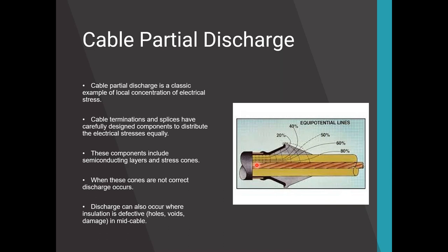The design of a cable and the stress cones and the terminations have a lot to do with limiting the amount of electrical stress that exists in the cables. So we saw a slide earlier, and we're going to see it in the next one, where the insulation is designed to keep those equipotential lines evenly dispersed. You don't allow them to concentrate. Well, the stress cones and the cones that are built around splices are designed to do the same thing.